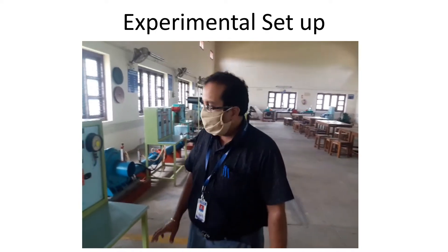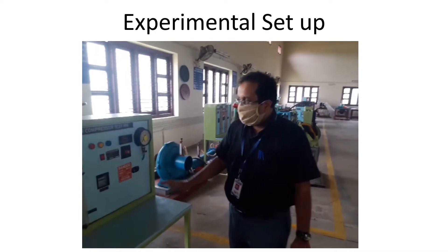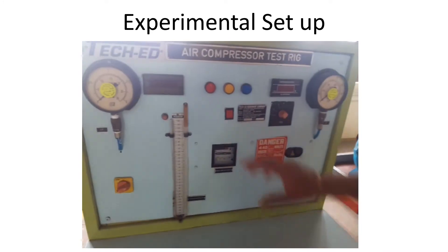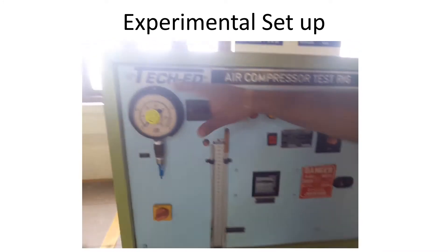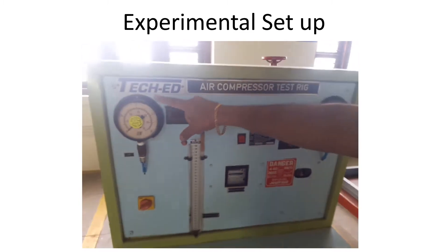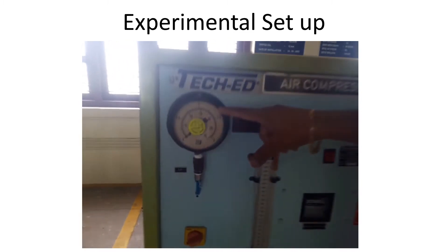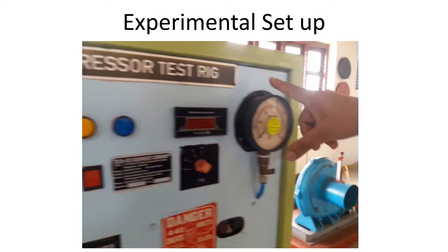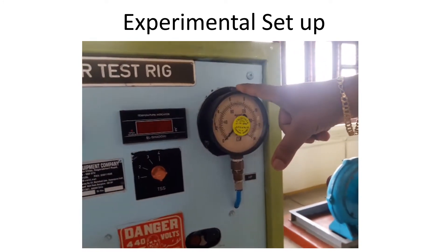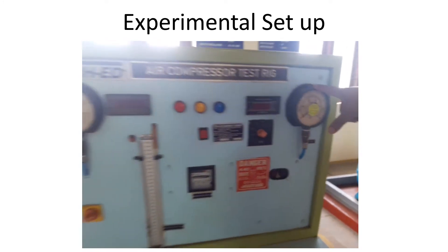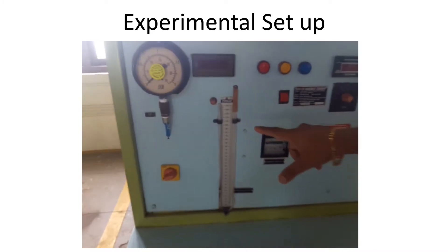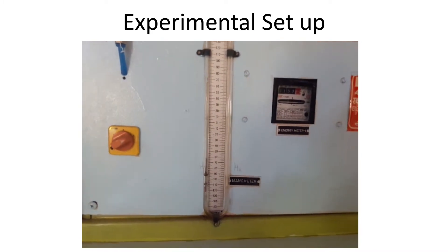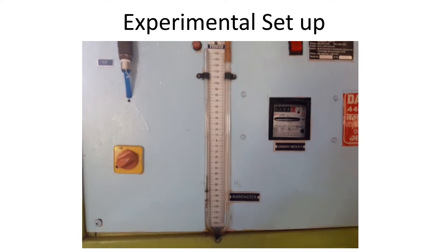Here is the experimental setup of the air compressor test rig. You can see that there exist two pressure gauges. One is used for checking the pressure of the low pressure cylinder, and the other is used for checking the pressure of the high pressure cylinder. There is also a water manometer, which is used to find out how much air has entered into the low pressure cylinder.